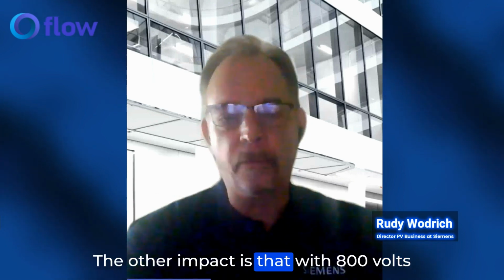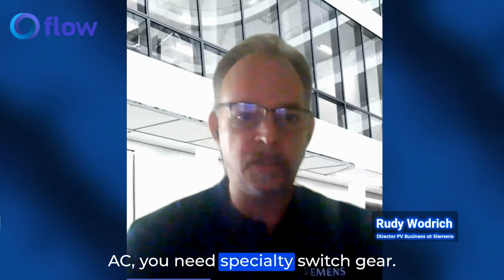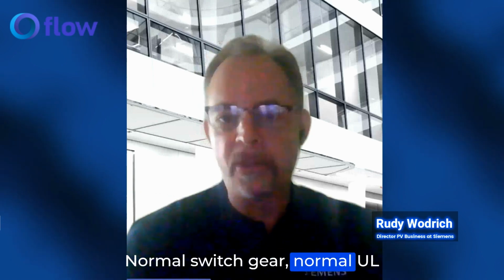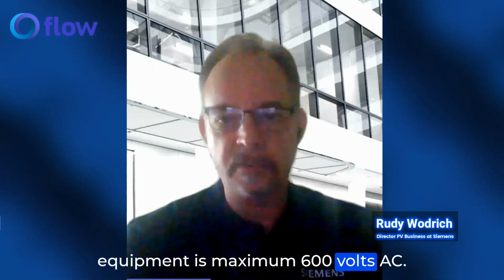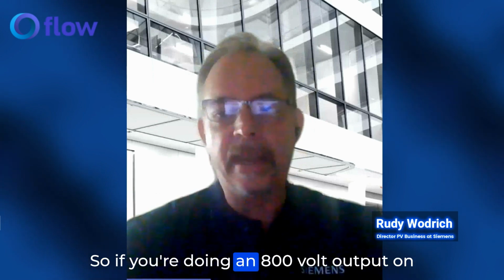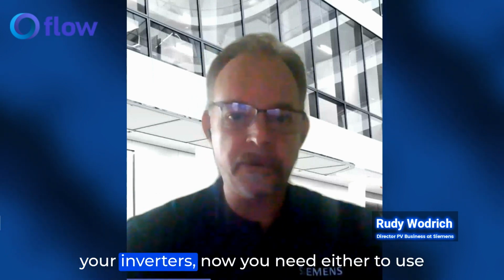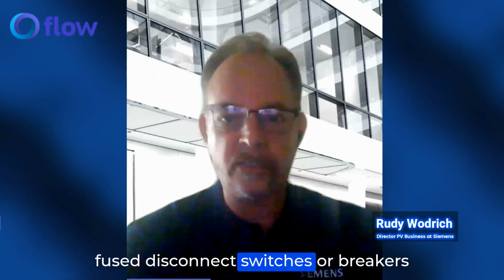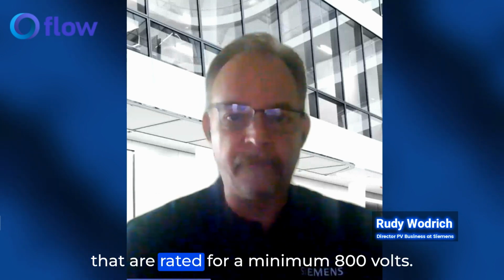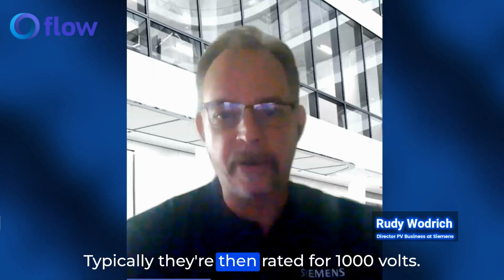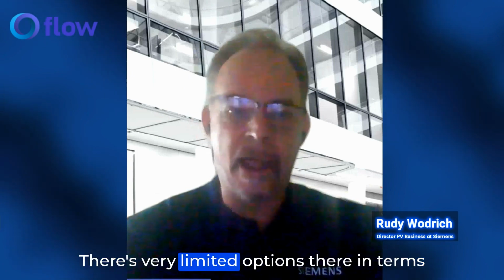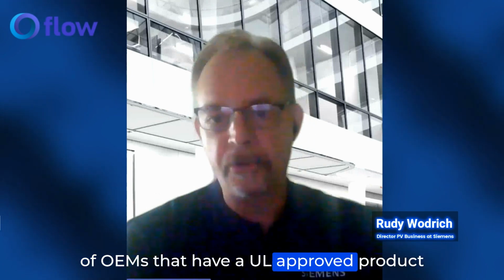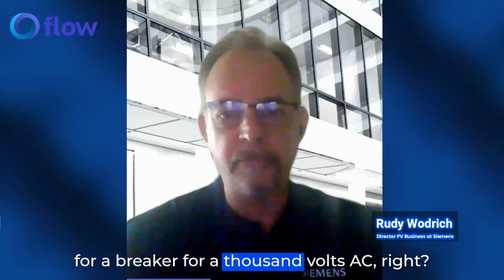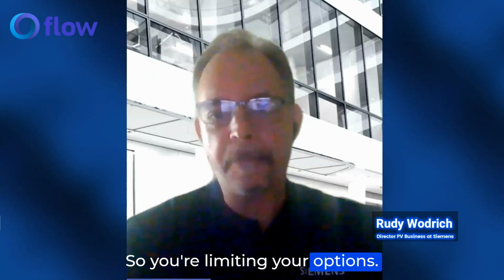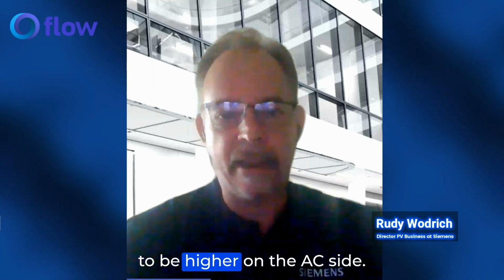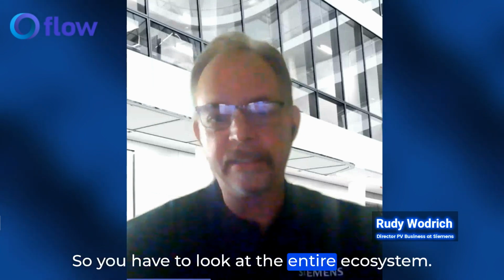The other impact is that with 800 volts AC, you need specialty switchgear, right? Normal switchgear, normal UL equipment is maximum 600 volts AC. So if you're doing an 800 volt output on your inverters, now you need either to use fused disconnect switches or breakers that are rated for a minimum 800 volts. Typically, they're then rated for 1,000 volts. There's very limited options there in terms of OEMs that have a UL approved product for a breaker for 1,000 volts AC, right? So you're limiting your options. Your cost of switchgear is going to be higher on the AC side. So you have to look at the entire ecosystem.